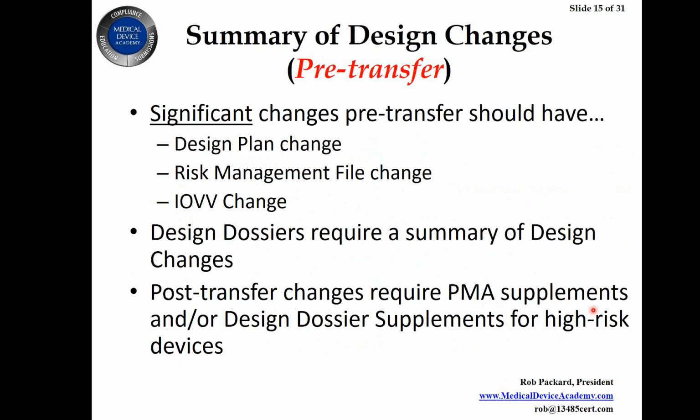And the design dossiers require a summary of design changes, but you don't really have to include every single design change prior to release of the product. They're mostly concerned with design changes post-transfer, post-market launch. It's good to identify some of the large changes that signified we changed the project plan, but you don't have to identify every single little tiny minute change that you made during the development process. Hit the highlights, because this is pre-transfer, pre-verification validation.